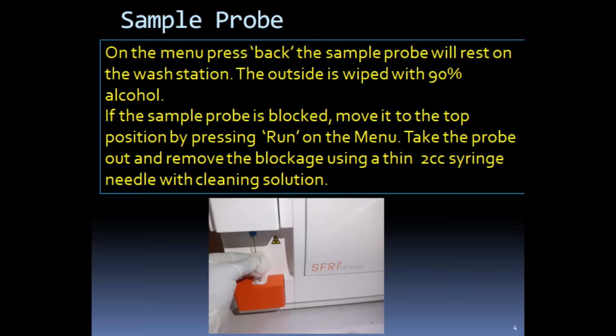For the sample probe maintenance, on the menu, press back. The sample probe will rest on the wash station. The outside of the probe is wiped with 90% alcohol. If the sample probe is blocked, move it to the top position by pressing run on the menu. Take the probe out and remove the blockage using a thin 2cc syringe needle with cleaning solution.